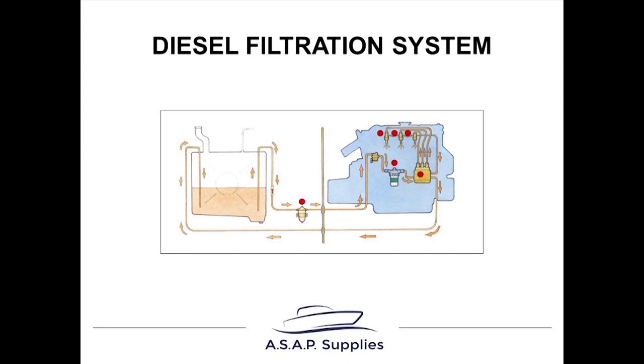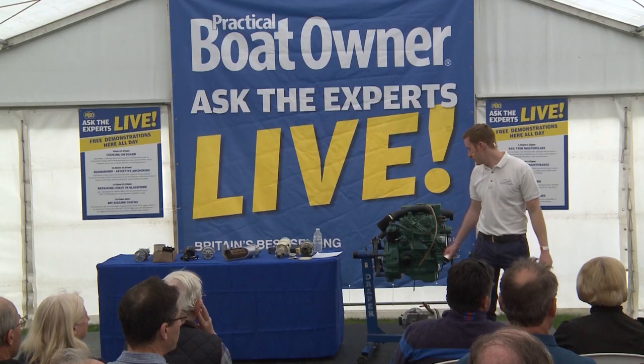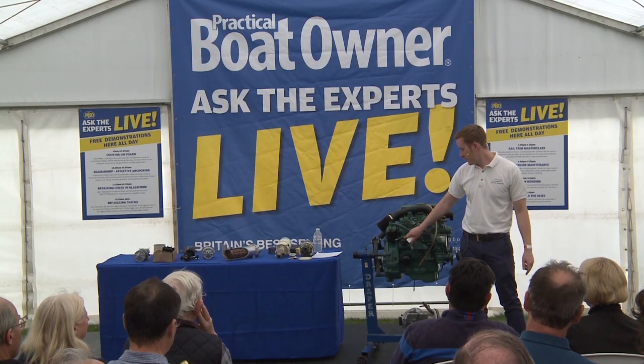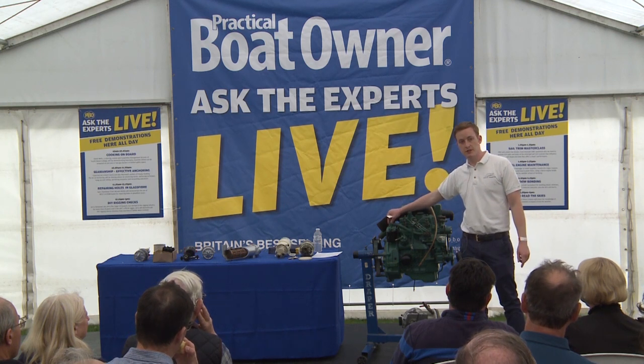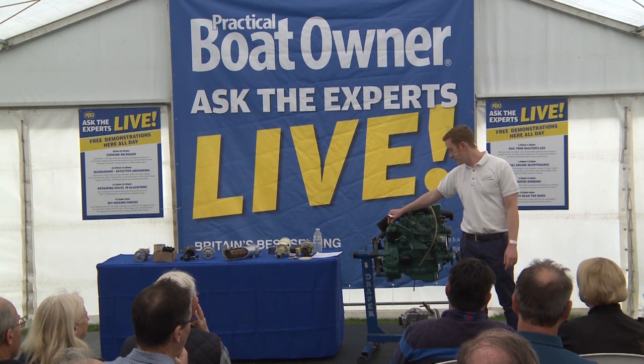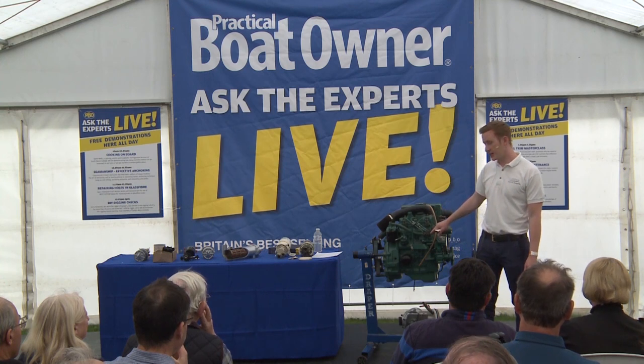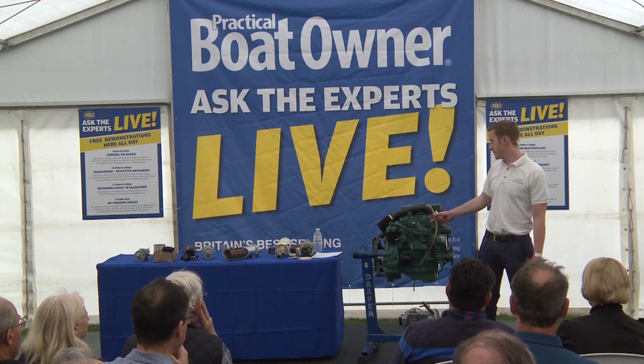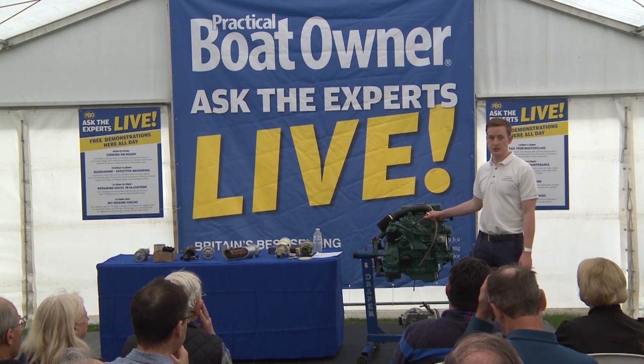So that's a typical diesel filtration system. There are more complicated versions, but that's pretty much the basis. You go from the fuel tank through a pre-filter, which takes the bulk of the dirt and water out of the system, then up to the lift pump on the engine, which would be there. That then goes through a secondary filter to take the finer parts out, and then into the fuel injection pump, which pressurizes it, and then that goes into the injectors.